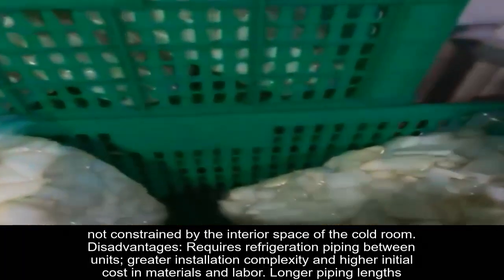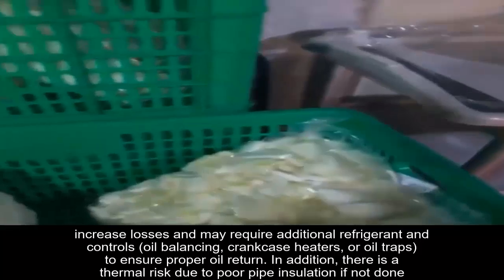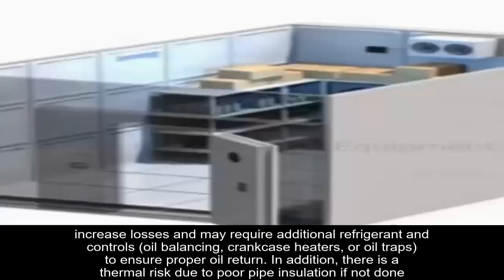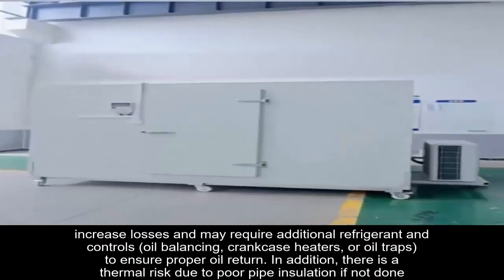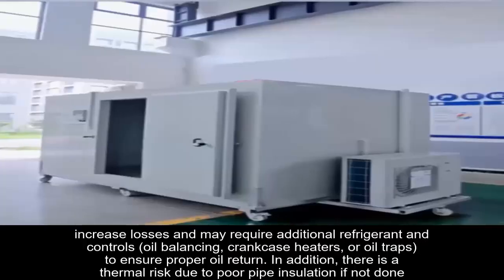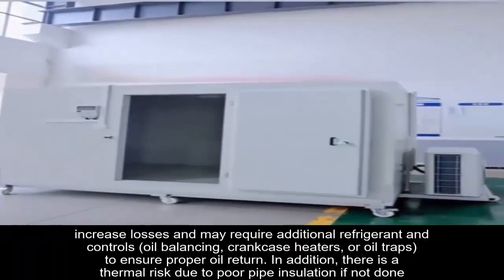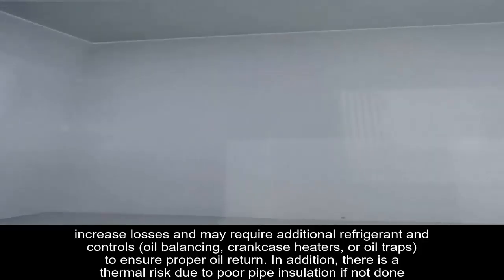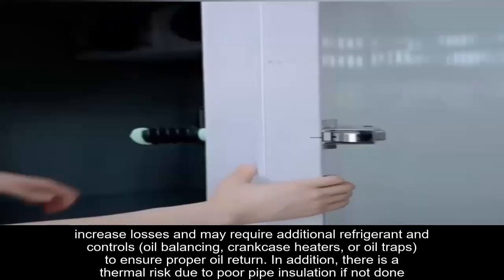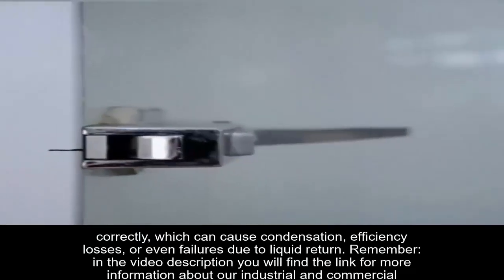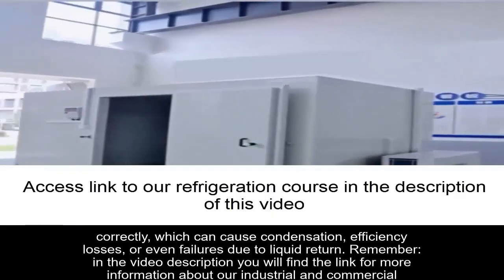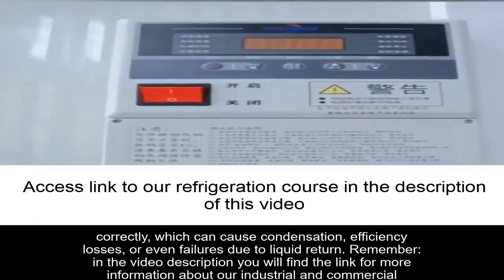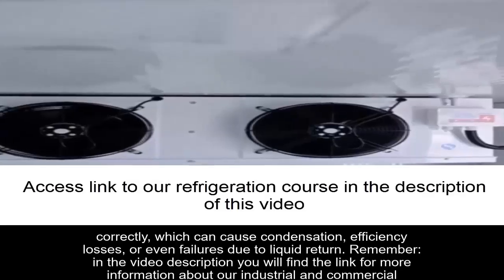Longer piping lengths increase losses and may require additional refrigerant and controls, oil balancing, crankcase heaters, or oil traps to ensure proper oil return. In addition, there is thermal risk due to poor pipe insulation if not done correctly, which can cause condensation, efficiency losses, or even failures due to liquid return.